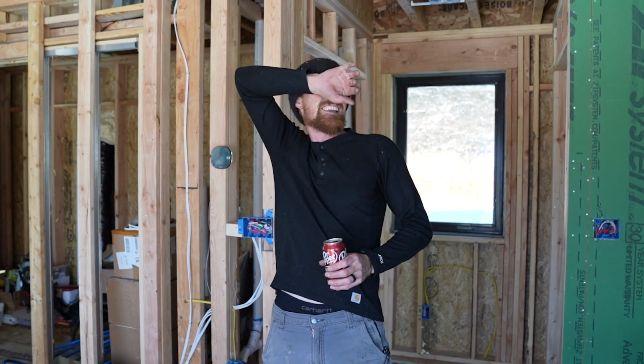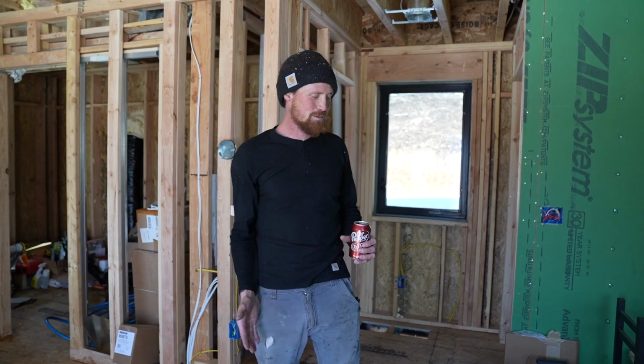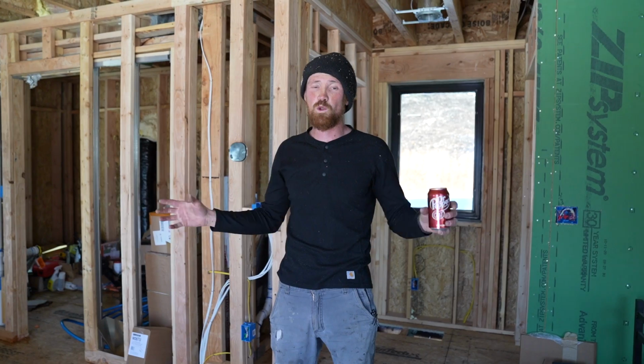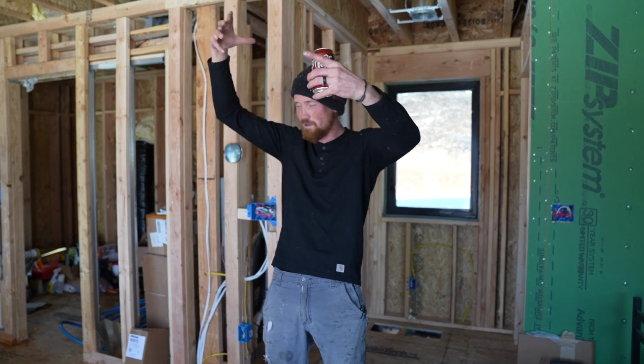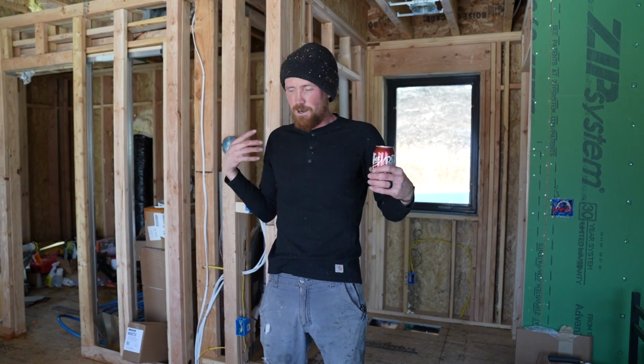But this electrical panel keeps tripping the breaker down there. We cannot figure it out. So I literally took the whole thing apart. I took the hot and the neutral bars out and made sure everything is dry, all the breakers are dry. We've taken it apart and put it back together 700 times by now. Brandon just went down to reset the breaker, and hopefully this is the last time we'll have to do this, and everything has been dried out and is going to work properly. Maybe.